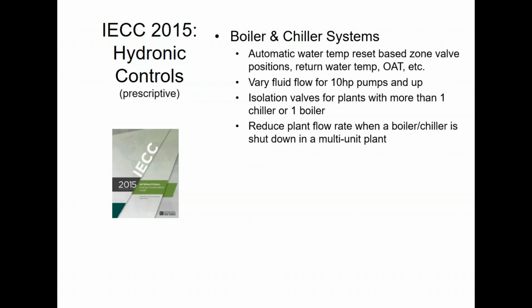Now, if you have two chillers in series, there's an exception for that. You can flow water through both of them if they're in series. But if they're in parallel and you only need one running, you shut off the other one and isolate it with valves. And that has to be an automated control system.